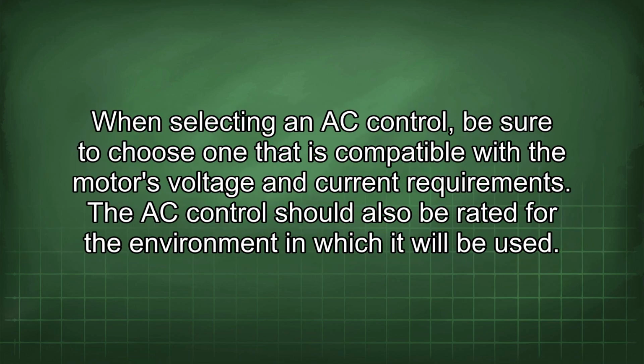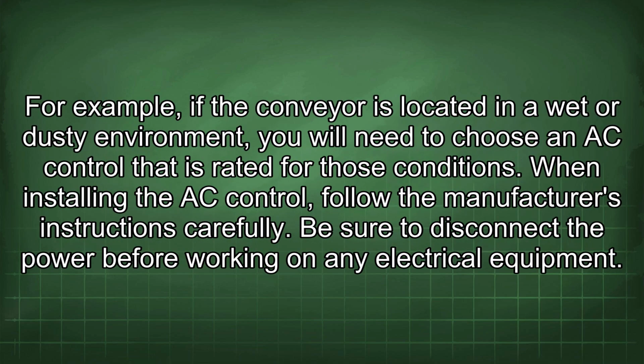When selecting an AC control, be sure to choose one that is compatible with the motor's voltage and current requirements. The AC control should also be rated for the environment in which it will be used. For example, if the conveyor is located in a wet or dusty environment, you will need to choose an AC control that is rated for those conditions.